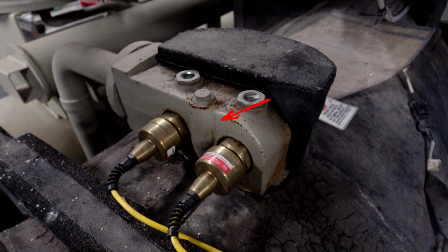But we also see the use of variable orifice valves. So we've got valves in the market now, something that York heavily uses, that is basically a butterfly valve, but it's not a normal butterfly. It's a modified butterfly valve that can be used to vary the flow and still create a pressure drop, but do it at a much larger scale. A scale that can be harder to do with an EXV body.